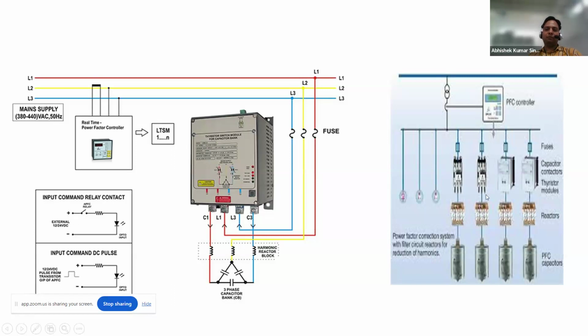suppose some big motor load has started, so the motor will magnetize its core. If the core gets magnetized, the power factor will go down, and if we have provided a contactor-based correction, then the correction time will be high. In that case, our MD, maximum demand, will shoot up. So to control that, we have to provide a thyristor-based panel, or a hybrid panel, that we already discussed. Now, there's one more important point: as you all see, this is a reactor.